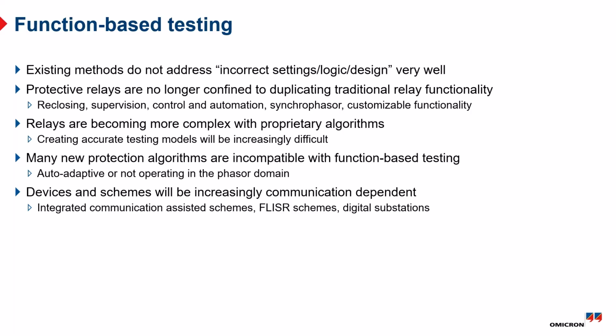Customers are comfortable enough with digital relays now that relay manufacturers do not necessarily have to follow those old functional definitions. So I just recently had a call from a customer who wanted second harmonic restraint on an overcurrent relay. This was an industrial plant with downstream transformers. When they energized the transformer, they didn't want the feeder overcurrent to operate. And with a modern digital relay, that's pretty simple to do. I just go into the SEL logic equations and write the equation, and there I created this new function. Problem is that nobody's protective relay setting software knows how to do that. So you end up having to create something manually or do something yourself rather than use the automations that are built into the test software.